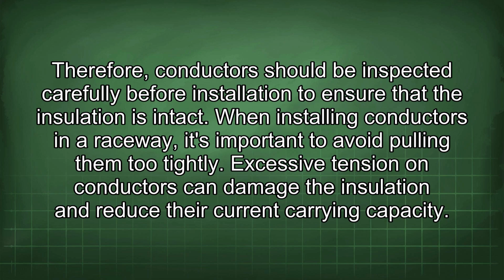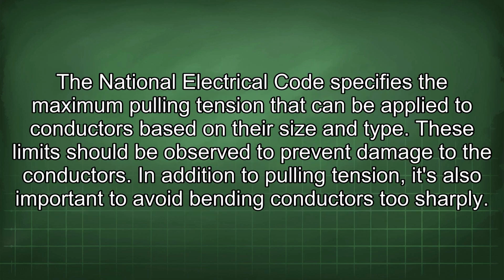When installing conductors in a raceway, it's important to avoid pulling them too tightly. Excessive tension on conductors can damage the insulation and reduce the current carrying capacity. The National Electrical Code specifies the maximum pulling tension that can be applied to conductors based on their size and type. These limits should be observed to prevent damage to the conductors.